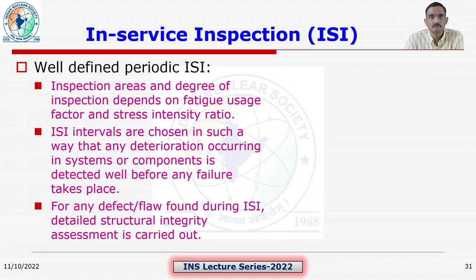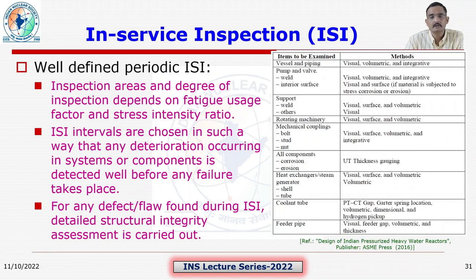For any defect or flaw found during in-service inspection, detailed structural integrity assessment is carried out. You can see in this table that for each component there is a well-defined in-service inspection program along with NDT methods, for example visual, ultrasonic, etc., for vessel, for piping, for supports. There are different well-defined examination methodologies - visual, surface, volumetric, and ultrasonic thickness gauging - for each critical component of the plant.